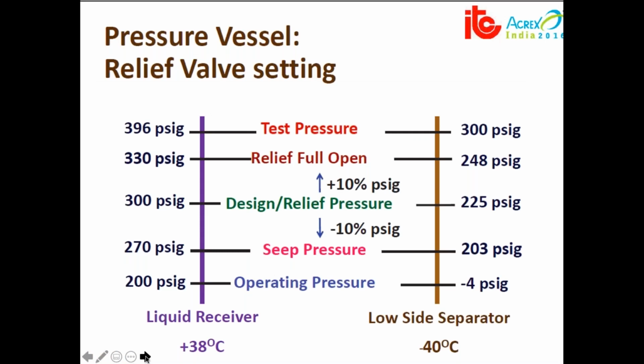Setting of the safety valve is very, very important. People do not know how to set the safety valve, at what pressure it is to be set. For example, if it is your liquid receiver, normally it is designed for 38 degrees centigrade ambient, 200 psig is the operating pressure, and the safety valve is set at 300 psig. The safety valve starts seeping at 270 psig.